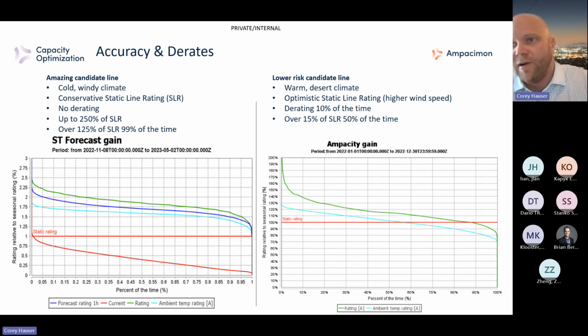As you can see on the graph at 90%, the dynamic line rating does fall below that static line rating value. So that does happen 10% of the time. But what you're really looking for here is the overall capacity gain coming from it, and making sure that gain, the other 90% of the time, offsets that 10%.